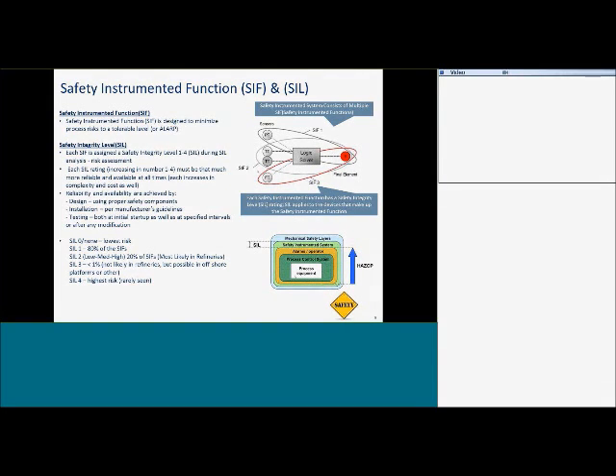So let's take a look at a few more terms. Safety Instrumented Function, or SIF, is something you may hear frequently talking with your SIS engineer. The SIF is when you've drilled down and down and down through those layers of the onion that we looked at earlier, and you arrive at a piece of equipment. On the top right, you'll see in this diagram you've got pressure sensors, temperature sensors, flow sensors. So your SIF is made up of sensors, logic solver, and a final element. And the final element is the automated valve package. So you may have many, many SIFs around even one piece of equipment. So each of these SIFs constitutes a small subsystem of the SIS.